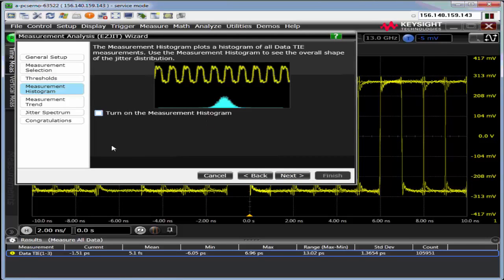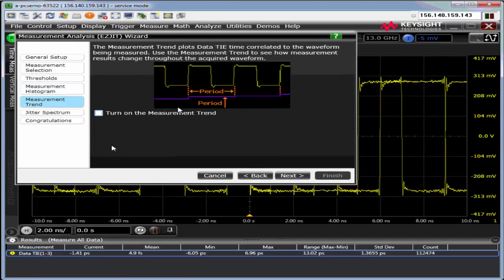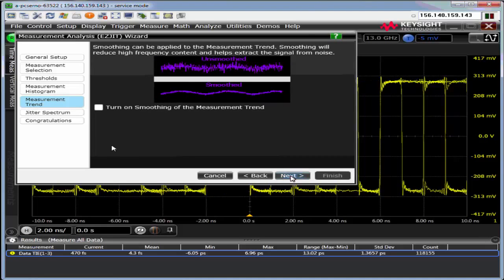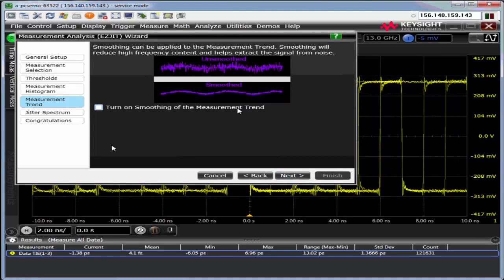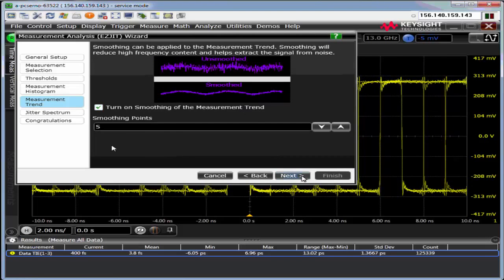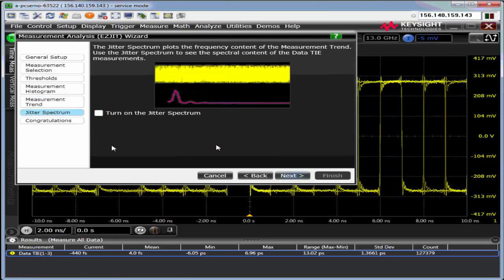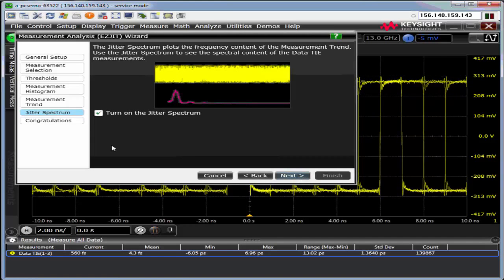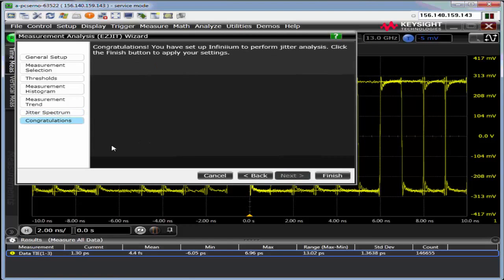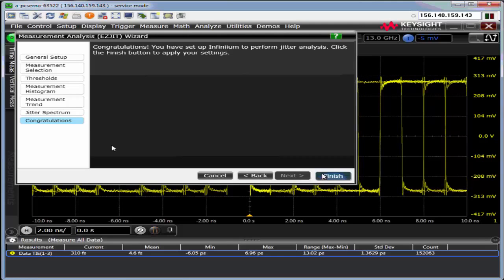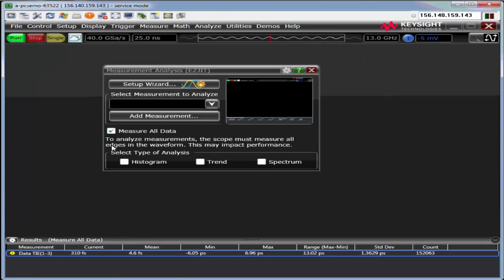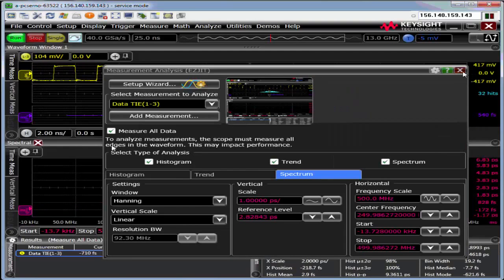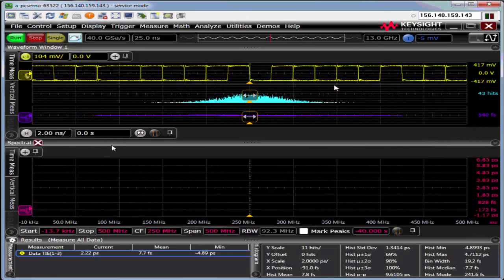I can turn on a histogram, turn on a measurement trend, smooth the measurement trend if I want, and turn on a jitter spectrum. Each of these tools is for a different purpose. Hit finish. And give the scope a second. And here I am making jitter measurements.